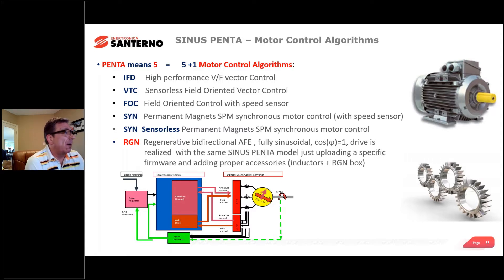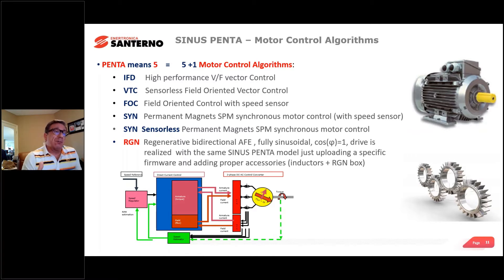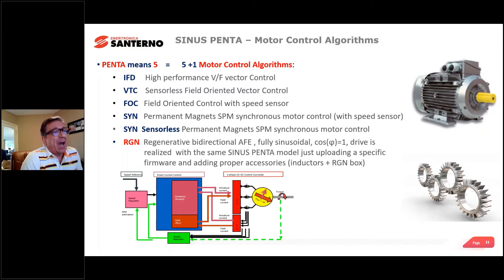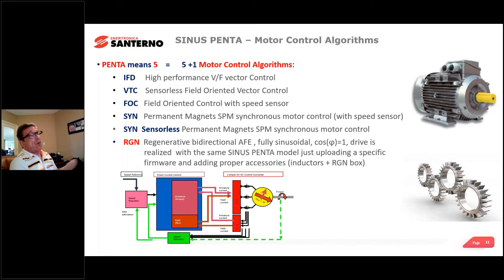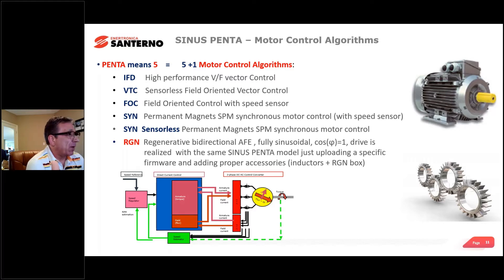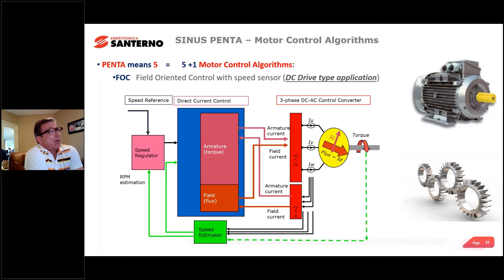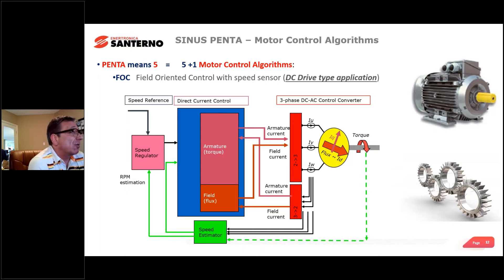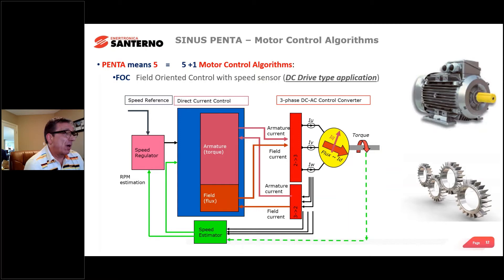Fourth is synchronous application — the drive can be used for newer-style permanent magnet motors, which are smaller with good torque. We can do this with a sensor or sensorless. Fifth, and probably the most unique, is regenerative — the drive can be used as a regenerative feeder, meaning it can be line interactive, almost acting like a solar inverter. Rather than putting excess energy into a braking resistor, the drive can actually use the grid itself as a line-interactive point.